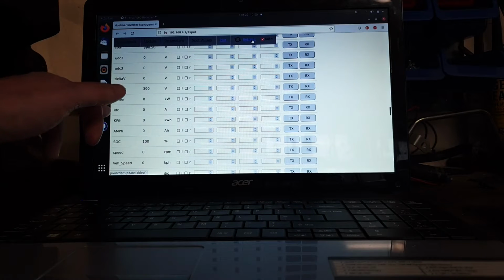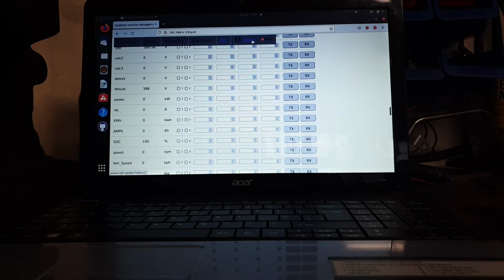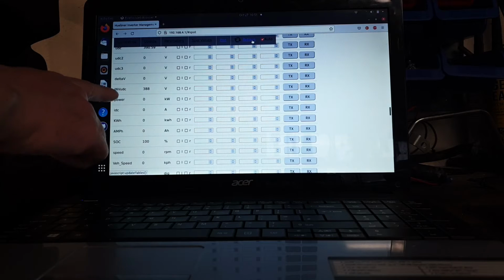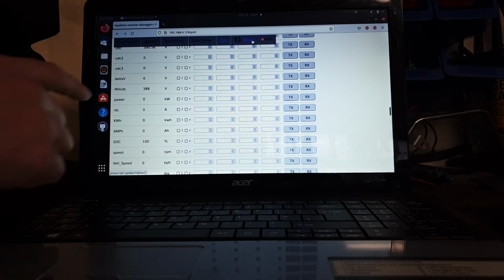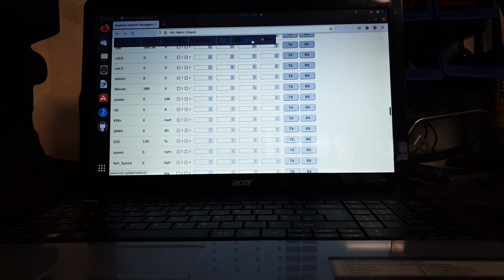Now at the minute we're not drawing any power, and we're not drawing any current as far as our shunt is concerned, but that should change fairly soon when our DC-DC converter in the PDM starts up. And if we come down here, we'll see our inverter UDC reading slightly differently, but that's perfectly fine - it's reading the voltage the inverter is measuring and transmitting via CAN to us. So that means we've got good communication with our inverter.